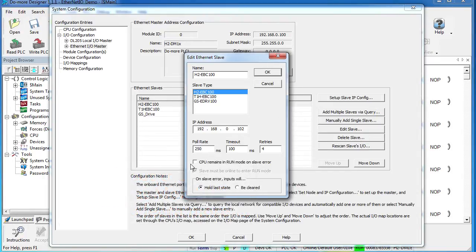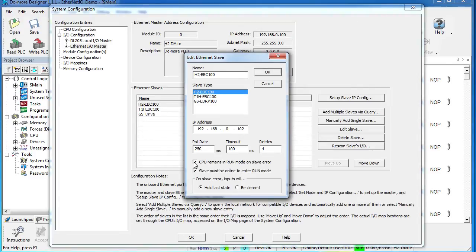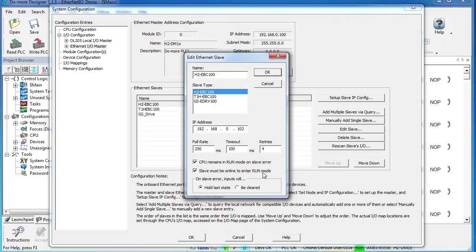In this dialog, you can also tell the CPU what to do if the slave has an error. If you tell the CPU to stay in run mode even if the slave has an error, then you get another option that says do you want the slave to be online when the CPU enters run mode.